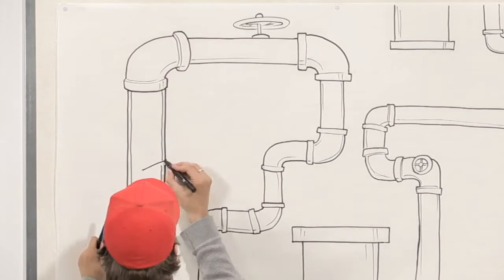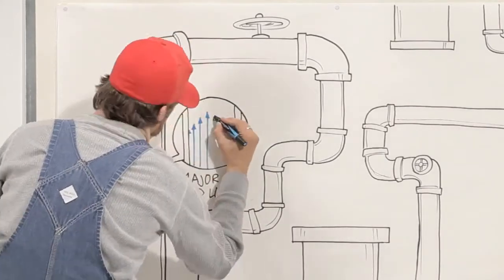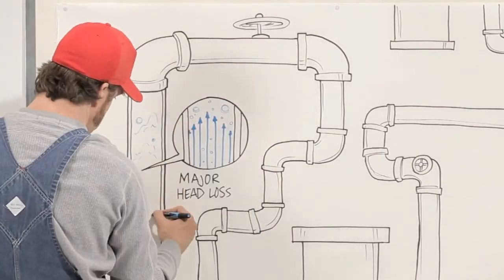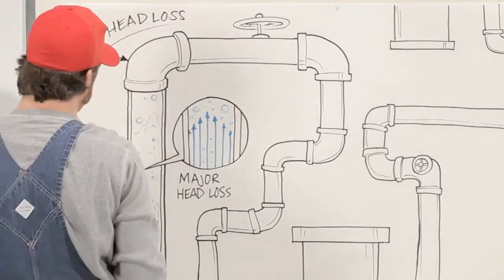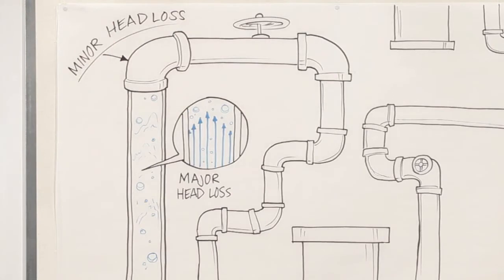Here, energy gets lost in two ways. By fluid drag against the walls of the pipe itself, which is called major head loss, and losses caused by going around corners, or through valves and joints, which is called minor head loss.